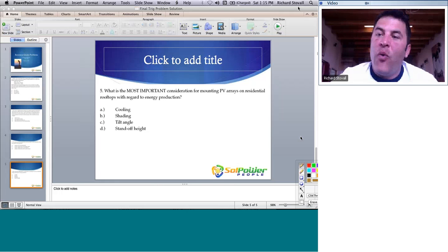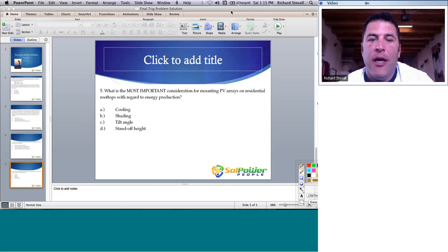We get a lot of questions in our courses. Students asking about, can you manually go out and adjust the tilts of your array four times a year to optimize production? And you know there are some systems that will allow for that. But if you look at the calculations in PV watts suggesting those angles, it really isn't going to make that much difference in your overall production.